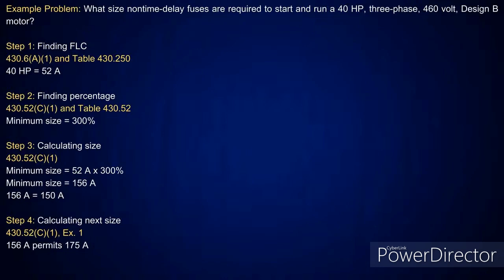When you go over and look at that, 430.6(A)(1) is going to be your starting point, because what it's going to tell you there is anytime you're sizing your conductors and your overcurrent protection device, you're going to use one of the tables in Tables 430.247 through 430.250. Now, in this case, if I was doing a 50 horsepower motor, 460 volt three phase, I look at Table 430.250, and I come down, pick up the 460 volt, and I come across, pick up 50 horsepower. It's going to tell you it's good for 65 amps.